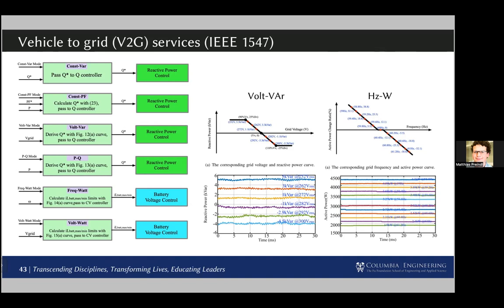Some of the services that can be provided by vehicles are aligned with the services that can be provided by solar inverters, which are specified in IEEE 1547. These are essentially reactive power control. We can have constant reactive power control, constant power factor control, or also dynamic control. These are modes that the inverter or the vehicle charger is put in, where, standalone, the local controller reacts to frequency, power or voltage variations and tries to stabilize the frequency or the local voltage and so on. These are already outlined in existing standards, and there are different modes that these converters can be set to and that are executed locally.